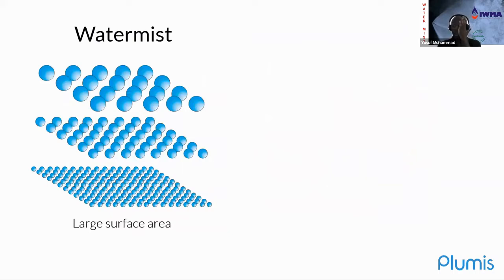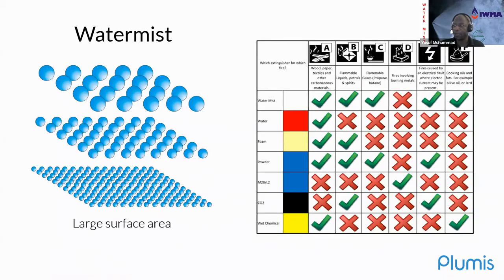So our entrance into the industry was very much inspired by work which was done previously into Automist. This is something which has been talked about earlier in the presentation. But water mist is so powerful because we're using smaller droplets of water. What happens is that primarily the water turns to steam, and in doing so, that displaces the oxygen that feeds the fire, as well as getting rid of the heat. So that's addressing two corners of the fire triangle.